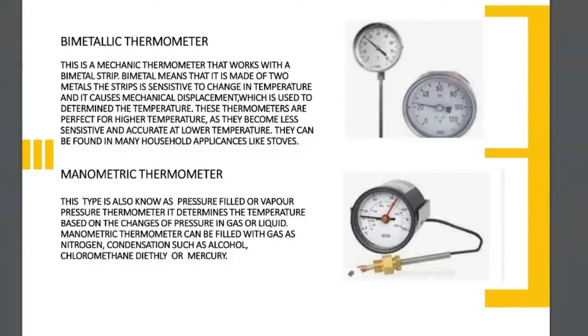So third is a bimetallic thermometer. This is a mechanical thermometer that works with a bimetal strip. Bimetal means that it is made of two metals. This strip is sensitive to changes in temperature, and it causes a mechanical displacement, which is used to determine the temperature. These thermometers are perfect for higher temperatures as they become less sensitive and accurate at lower temperatures. They can be found in many household appliances like stoves.